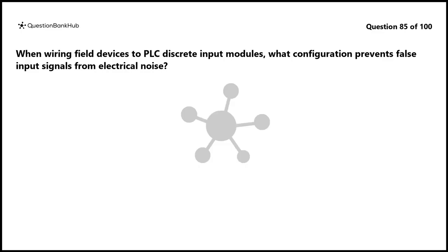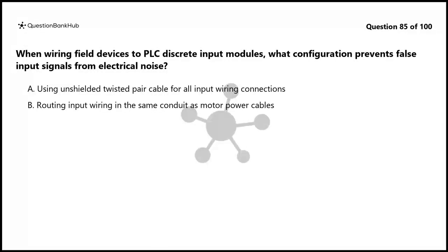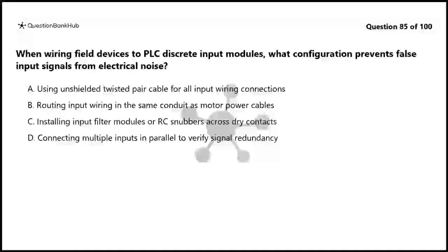Question 85. When wiring field devices to PLC discrete input modules, what configuration prevents false input signals from electrical noise? A. Using unshielded twisted pair cable for all input wiring connections. B. Routing input wiring in the same conduit as motor power cables. C. Installing input filter modules or RC snubbers across dry contacts. D. Connecting multiple inputs in parallel to verify signal redundancy.